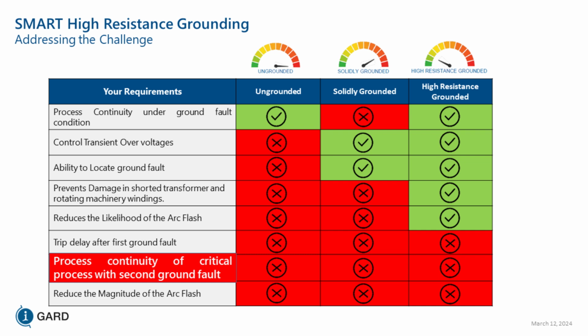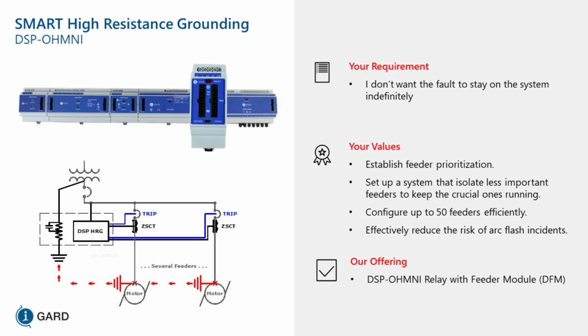When you have one fault, you can still operate with one fault because the code says you don't have to isolate. If you look at 250.36, it says if you limit your fault current to a low value, and if you're less than 1 kV, you don't necessarily have to trip. Whereas Canada says in 10-300, it used to be 10-1100, that with current limited to a low value, 10 amps or less on systems 5 kV and below, you don't have to trip. NFPA 70E and Z462 say that if you have a high resistance grounded system, you have an arc flash mitigation technique, so you don't have to trip.